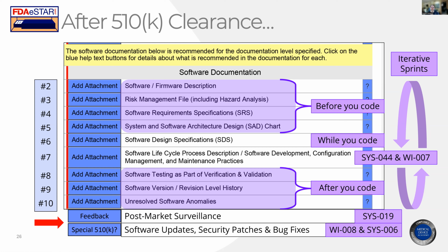In addition to the things that you're going to probably do right away, after you launch your product commercially, you're required to do post-market surveillance. Now, the FDA doesn't currently have a post-market requirement in the QSR, but the QMSR does because it incorporates by reference ISO 13485. Clause 8.2.1 is post-market, and the FDA did not say you're getting out of that. They are allowed to look at those records. You do have to comply with it under the QMSR, and you will be expected to do post-market surveillance.